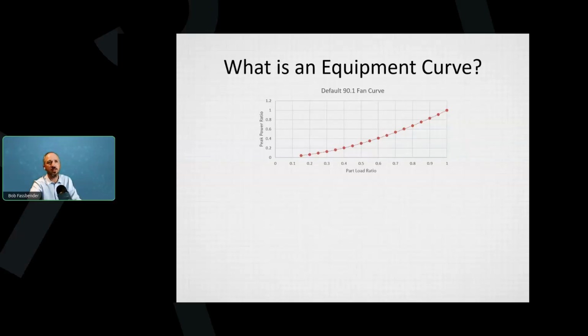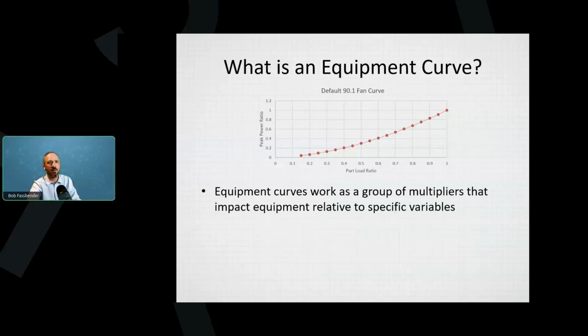Okay, so this is the standard curve for a 90.1 fan. This is also important for modeling and for predicting the savings that you think you'd get. So an equipment curve is basically a set of multipliers. If this was a 100 kilowatt fan, we would look at the 1 in the lower right corner, and that's part load of 1 and peak power ratio of 1. So at full power, it's at 100 kilowatts. It's a big fan.